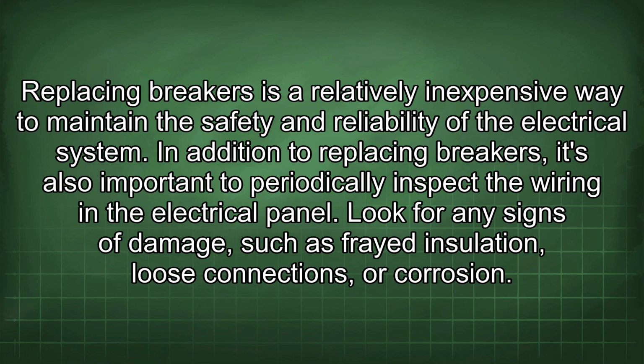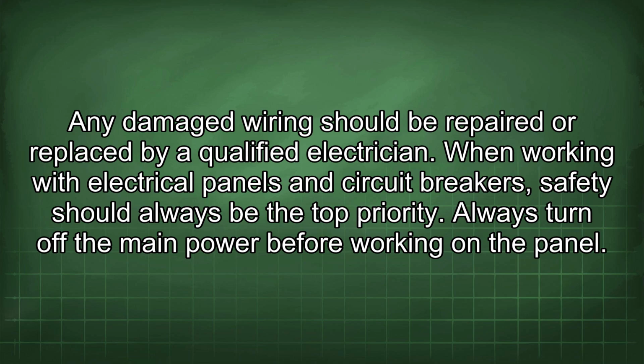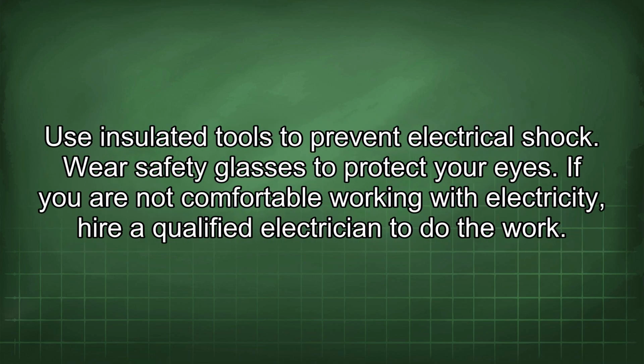In addition to replacing breakers, it's also important to periodically inspect the wiring in the electrical panel. Look for any signs of damage, such as frayed insulation, loose connections, or corrosion. Any damaged wiring should be repaired or replaced by a qualified electrician. When working with electrical panels and circuit breakers, safety should always be the top priority. Always turn off the main power before working on the panel. Use insulated tools to prevent electrical shock. Wear safety glasses to protect your eyes.